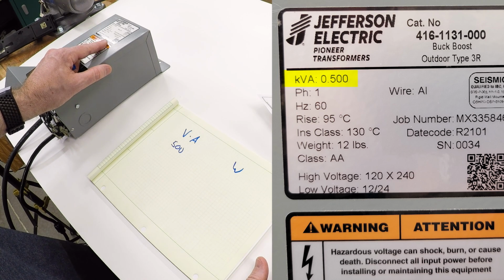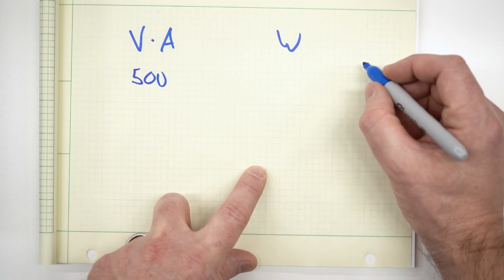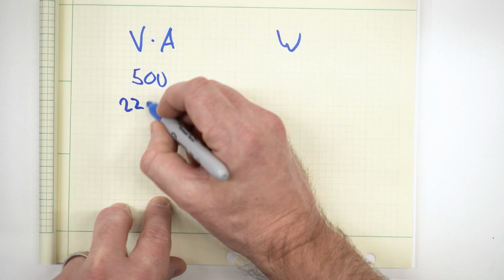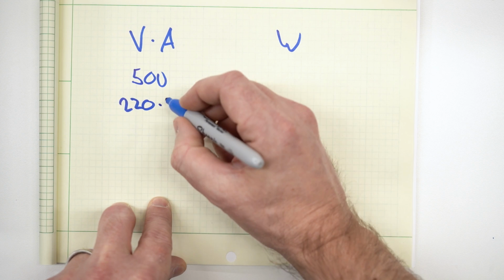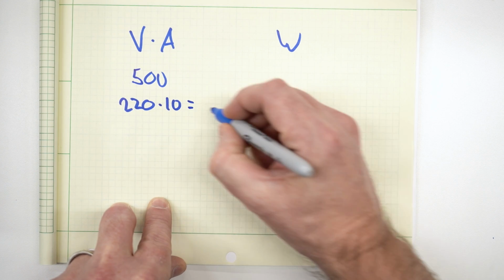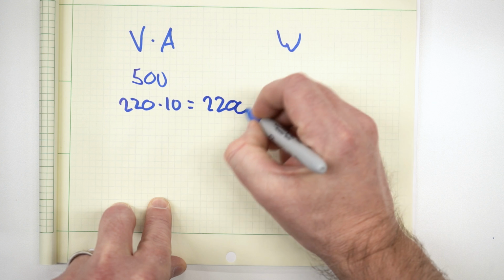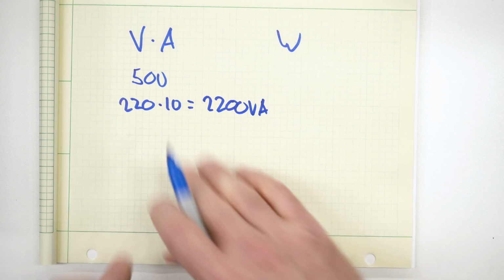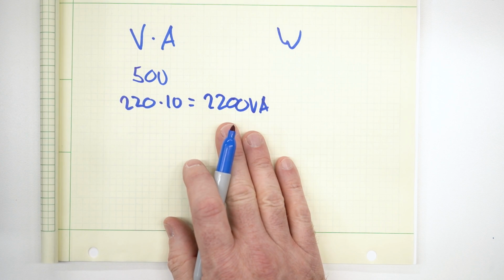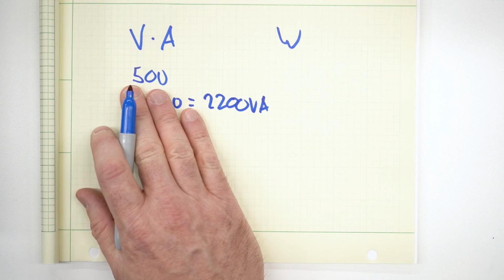That doesn't make sense, because what I'm actually trying to run here is a 220 volt device that requires 10 amps, which should be 2200 VA. So why don't I need a 2200 VA transformer for this? Why am I able to get away with a 500 VA transformer?